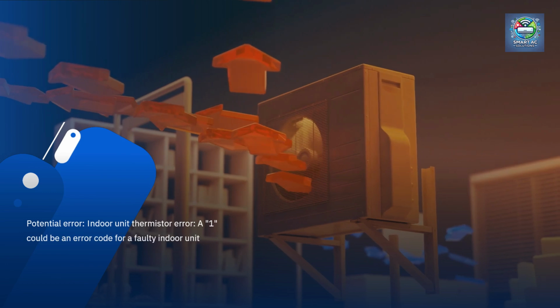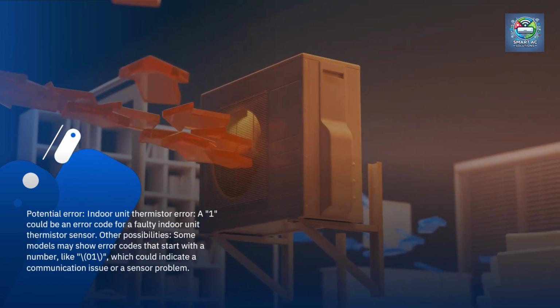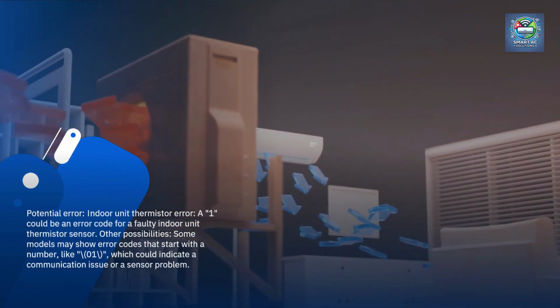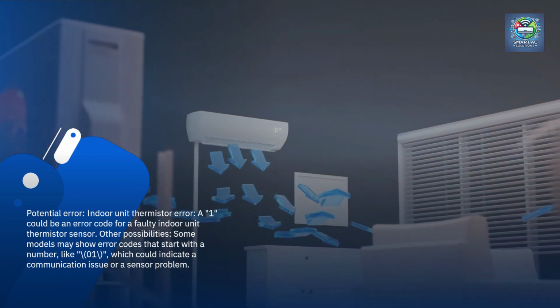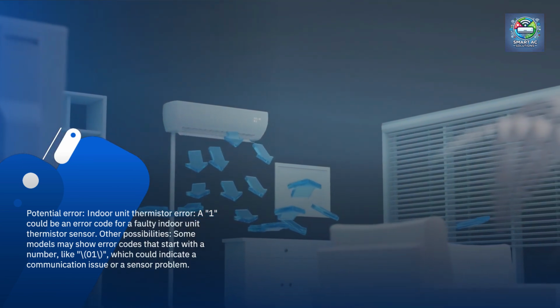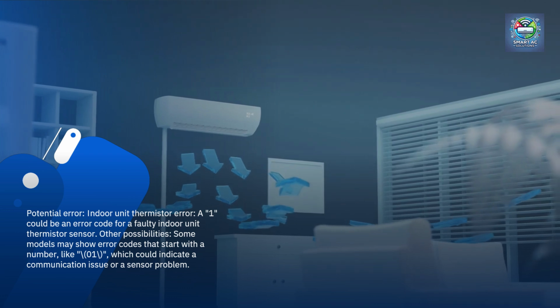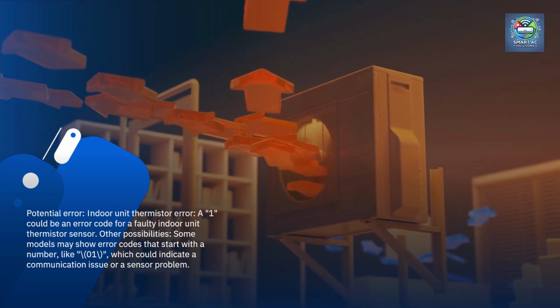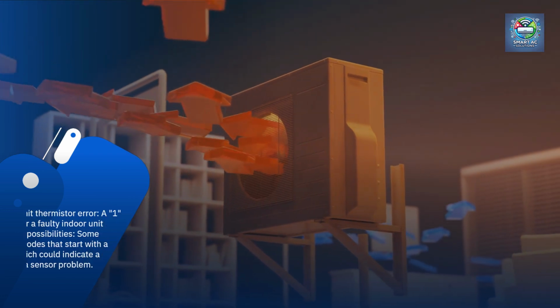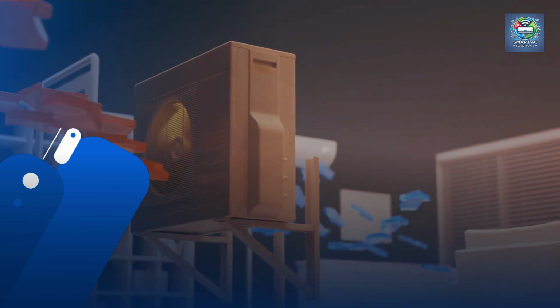Potential error. Indoor unit thermistor error. A 1 could be an error code for a faulty indoor unit thermistor sensor. Other possibilities. Some models may show error codes that start with a number, like 01, which could indicate a communication issue or a sensor problem.